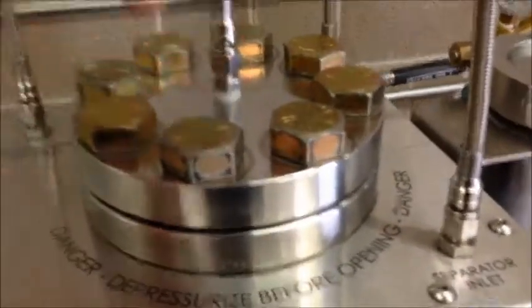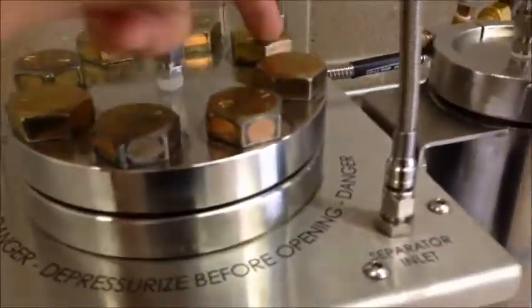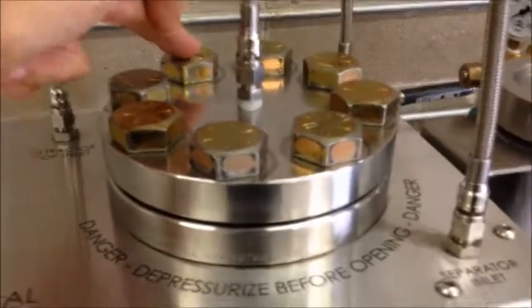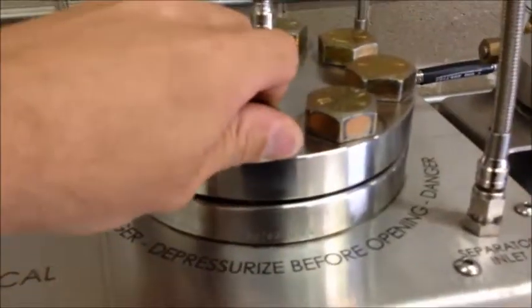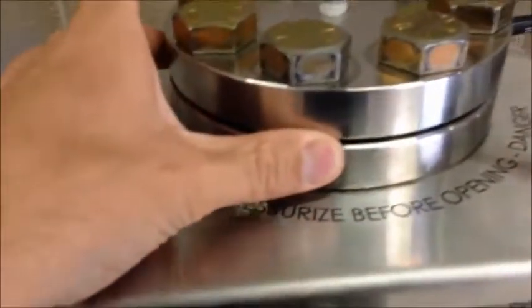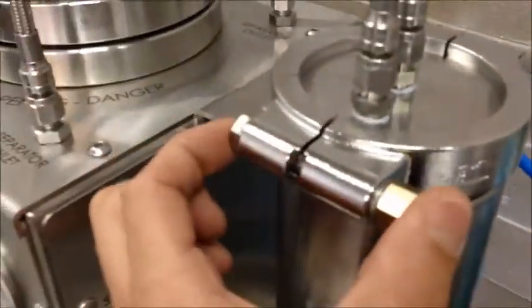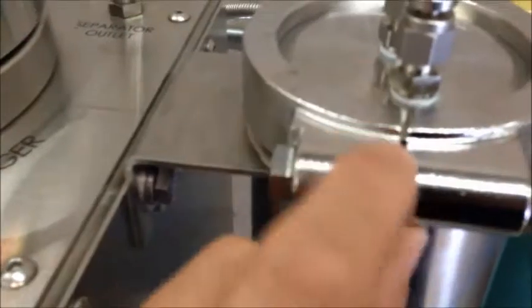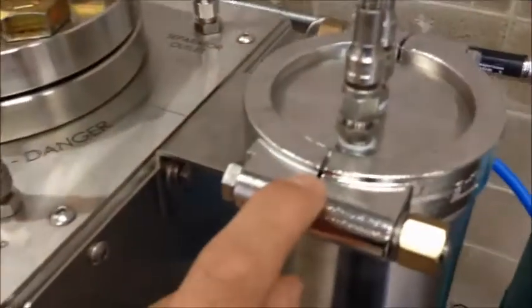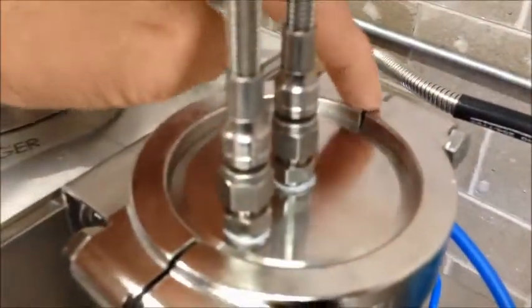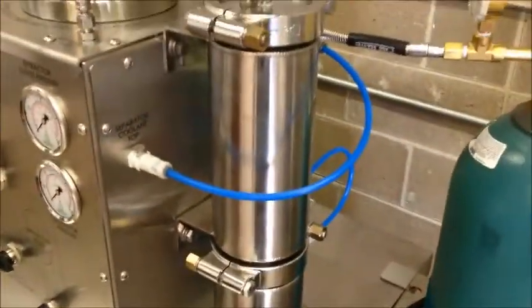When you're putting these bolts back in, hand tighten them all, then you'll do a star pattern really quick. Tap, tap, tap, tap, tap, tap, tap, tap, and then once around. You do not need to over tighten these. That's what the O-ring in here is for. Same with the separator. There's gaskets in here, so when you tighten these up, there should be an 1/8 to a 1/16 spacing right there, just like you see here. Do not have metal to metal. That will crush your gaskets.